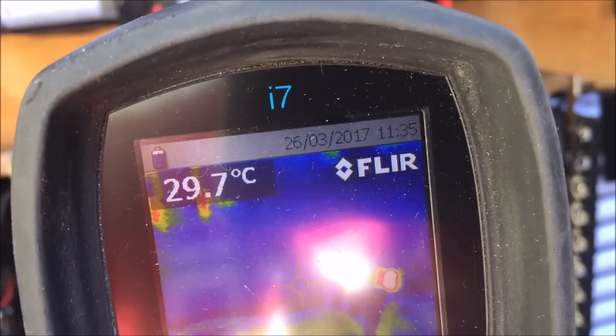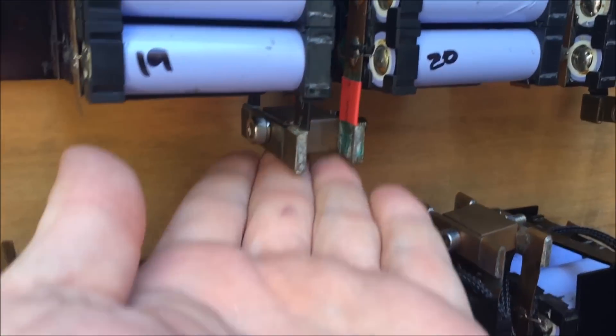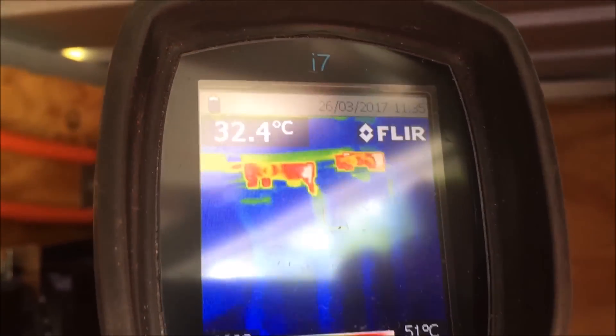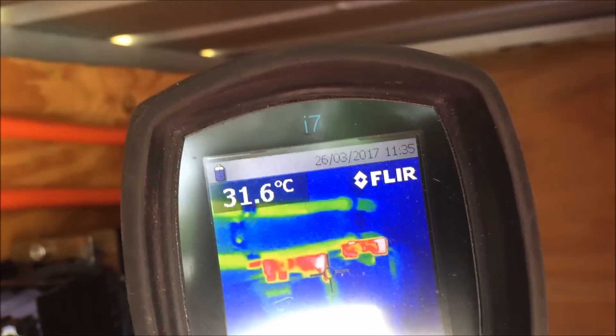The connectors are getting quite warm. That one's not horrible, that one was not horrible, but it looks like it's getting quite warm. Now if you go up the top here, those two connectors at the end — they're a little bit warmer. Let me get a crosshatch to get a temperature reading.